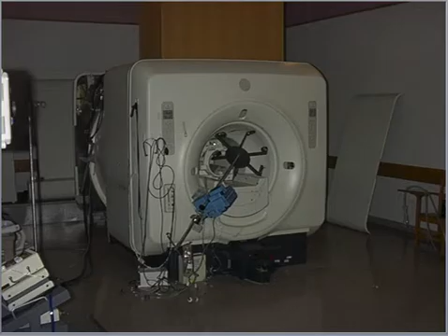When I worked at Chelsea Hospital, when they were redoing, or maybe they were doing something to the MRI unit, I don't remember, a maintenance worker brought in a step stool to do some work in there, and it yanked the step stool into the scanner. Luckily, it was after hours, so there wasn't anybody in there, but it can still cause severe damage to the scanners, and depending on how strong the magnetic pull is, that can cause a big problem. Like I said, that magnet's always on, and to completely shut everything down, they have to do what's called a quench, and that's going to release all of the gas out of the MRI unit, and it costs like $500,000 to get that fixed if you have to completely quench or emergency shut that MRI down.